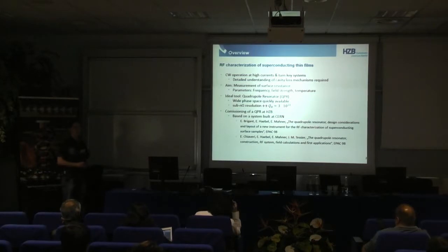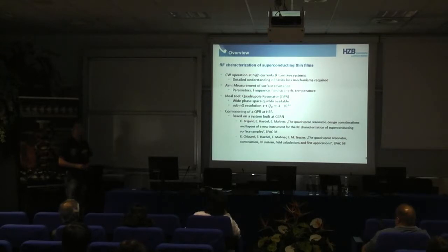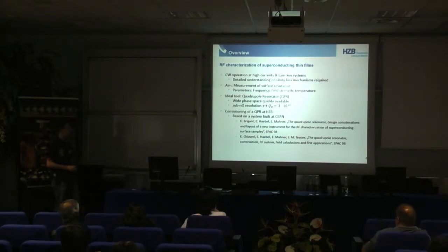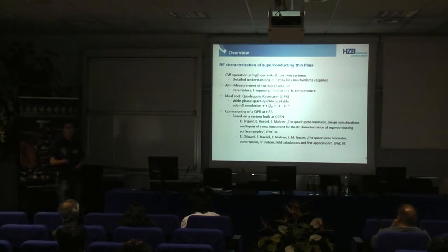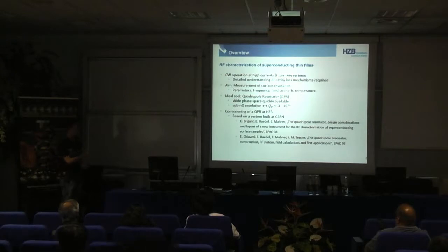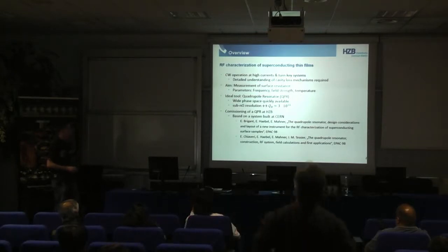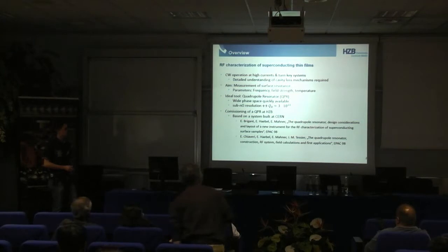I can present an ideal tool to do this. With the quadrupole resonator, we have a wide phase space available of frequencies, temperature, and field. These measurements can be done with sub-nano-ohm resolution, which corresponds to a high Q of about 10 to the 11. Therefore, we are commissioning a QPR at HZB, which is an optimized version of the already existing and very successful system at CERN. The original design comes from CERN and has then been adapted to the HZB design.